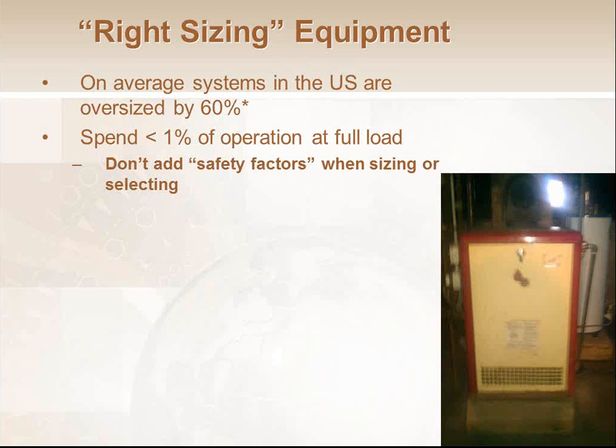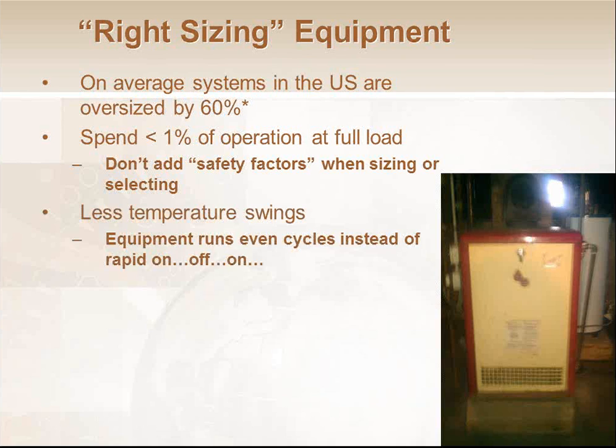The other thing is you're never at full load, right? It happens less than 1% of the year, at like 3 a.m. in the middle of January, for a few hours, maybe a couple times a year. So rounding up to larger boiler sizes doesn't make any sense. Whatever the load calcs come out to, put that size boiler in. If you want to round it off, round it down. Stop rounding it up. All the safety factors you built into your load calcs, you're already oversized anyway.